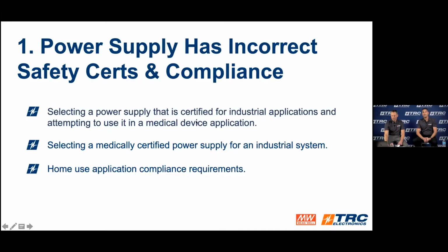Right, Brian brings up a good point. Here you have a scenario where you have to have a medically approved supply to get the lower leakage current, and then you have other requirements for the ITE spec. Typically, especially in medical equipment, we can combine different voltages into one product. Modular power supplies has been something we've done with a lot of success. With a modular power supply you can have your 12, 24, and 5 volts split up on the DC end, but only one connection to the AC plug. That gives you a lower overall leakage current while still supplying all the power to the various devices.